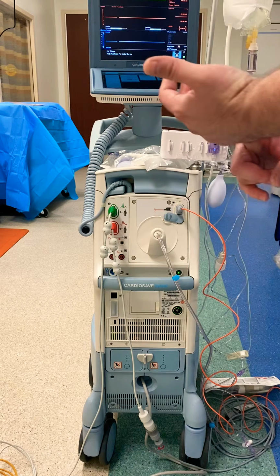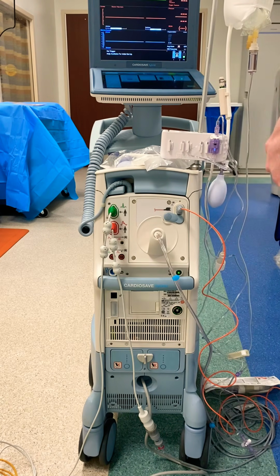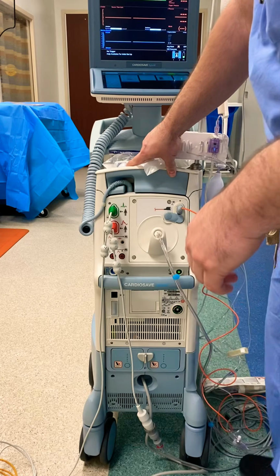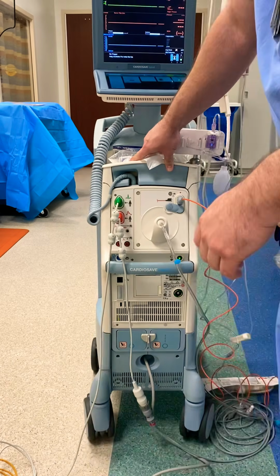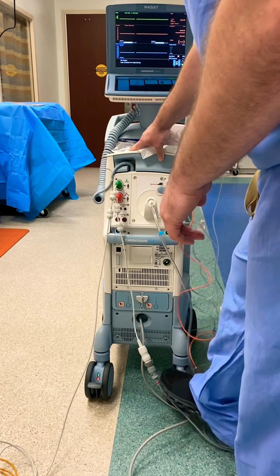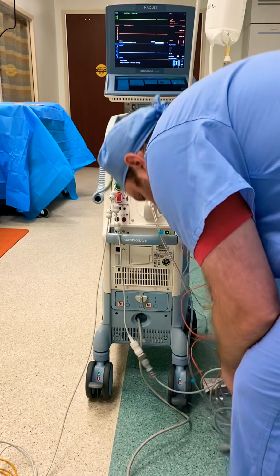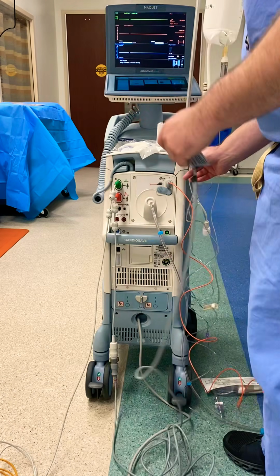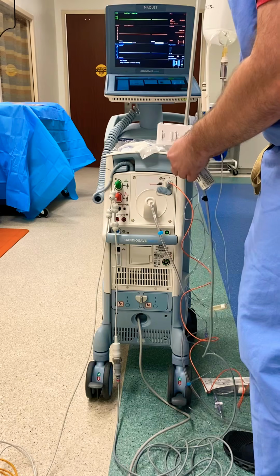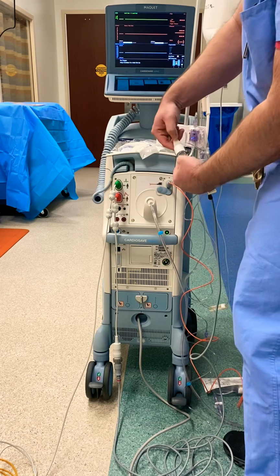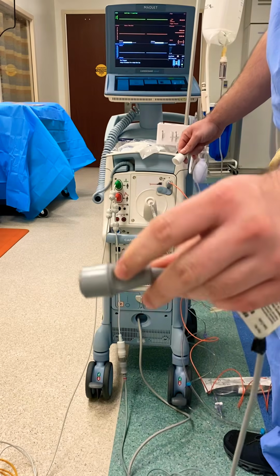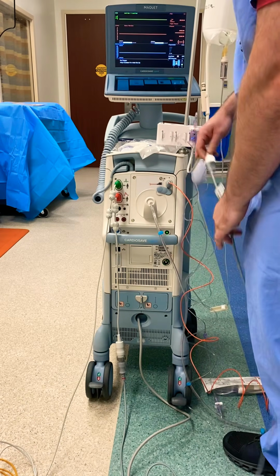At that point, you have an EKG, you have a transducer that is going. Your pressure waveform will be coming from the fiber optic cable that is in. Your helium is running. So now I'm going to show you how you can put this thing in rescue mode and make it smaller. I'm just going to roll it back some. So your transducer is connected. There's little ribs on there. You can line those up. You can see them on there. There's some on here too. So these will be connected to the patient.